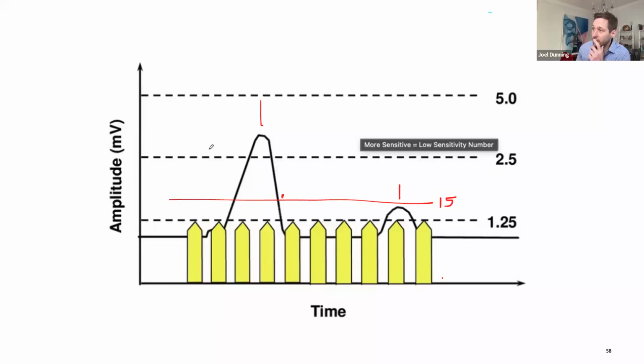You really have to understand how tall these R waves are before you set your sensing. But in general, if you have 2 millivolt R waves, you're really going to have to set your sensing quite low, 1 millivolt. If your R waves are 12, then your sensing can be a lot higher threshold at 6 millivolts. In general, the lower the fence, the more sensitive the device is. So it's kind of an inverse relation.